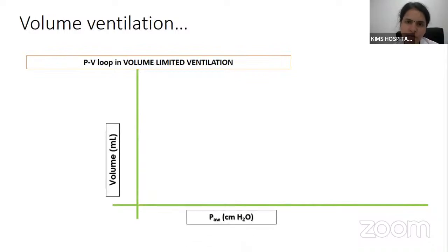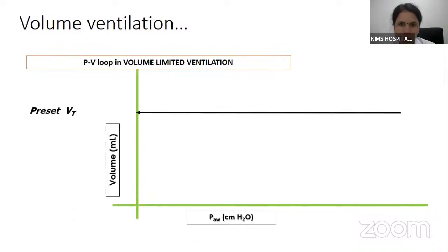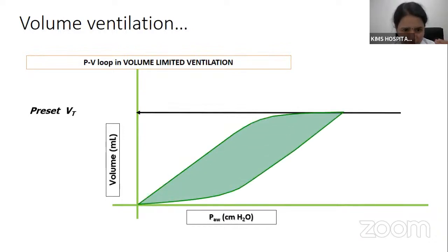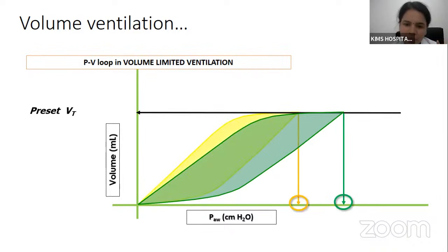So with each breath, the baby can achieve different tidal volumes, leading to very erratic ventilation and CO2 elimination. Whereas when the tidal volume is preset, we have determined that this is the volume that needs to be delivered in each breath. For example, for an adult, 500 ml is the set tidal volume. So when the compliance changes, the ventilator simply delivers the same tidal volume.